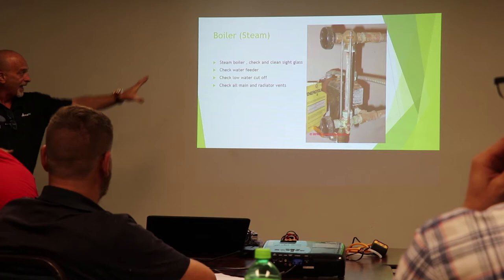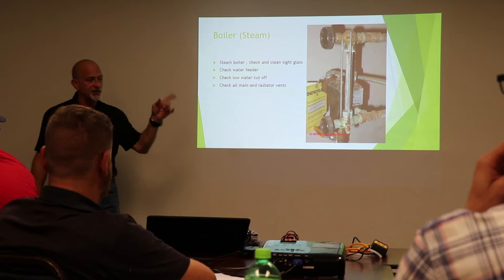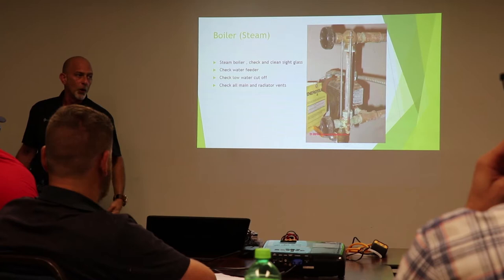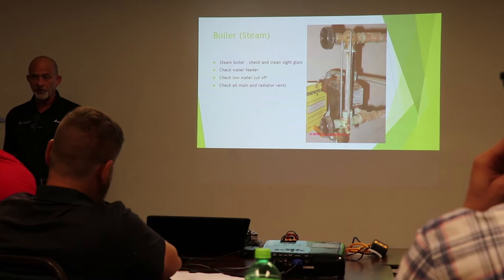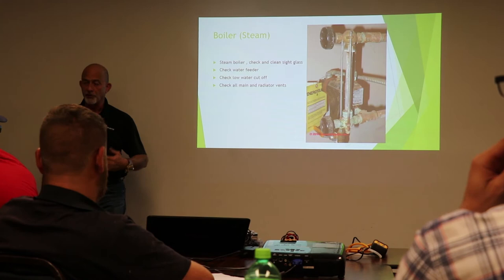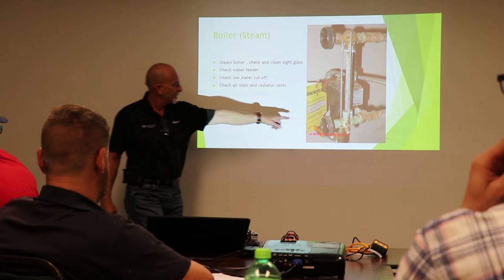But that sight glass on a steam boiler tells you visually how much water's in the boiler. Steam boilers, if you don't work on them or haven't worked on them, they're completely different than a water boiler. A water boiler's a sealed system. Steam, we always have to put water in. Very critical that our low water cutoff and our feeder are working correctly. This, you'd have to pull these little rods out, loosen up these nuts.